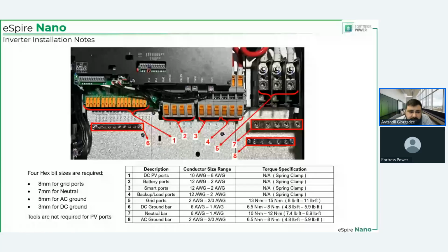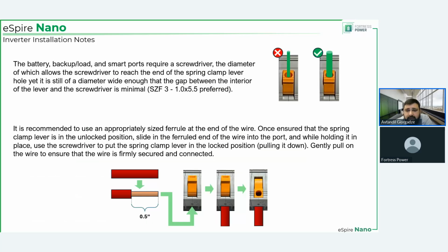Then some of the tools that you're going to be using are right here, on the left side, bullet points, and also the torque specs are given here. Spring clamps are there for the smart loads, backed up load ports, battery ports, and PV ports. For those, you don't need special tools, except for the battery and smart port, where you'll need a flathead screwdriver. The flathead screwdriver is such that this inlet diameter and the screwdriver diameter are very close to one another.